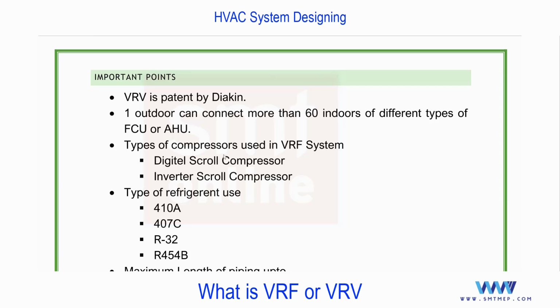Next, type of compressor. This is important. It depends on capacity or the number of indoor units. The capacity in general is up to 40 or 42 TR, and within that you need to match the indoors. Don't jump to conclusions. We have the possibility to connect up to 60 indoors, but definitely as per the capacity of the outdoor. If the outdoor capacity is 20 TR, we cannot connect more than 20 indoors of 1 TR, right? In that way.